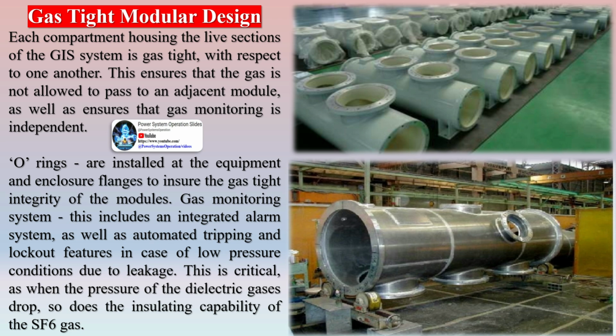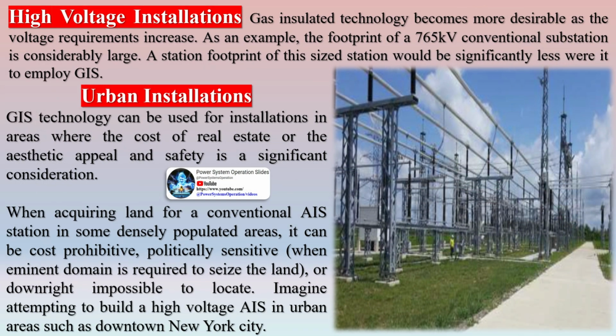This is critical, as when the pressure of the dielectric gases drops, so does the insulating capability of the SF6 gas. Gas-insulated technology becomes more desirable as the voltage requirements increase. As an example, the footprint of a 765 kV conventional substation is considerably large. A station footprint of this size would be significantly less were it to employ GIS.